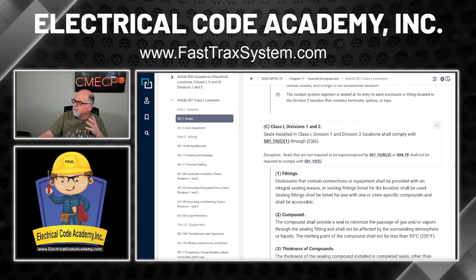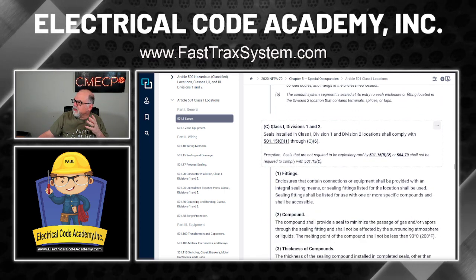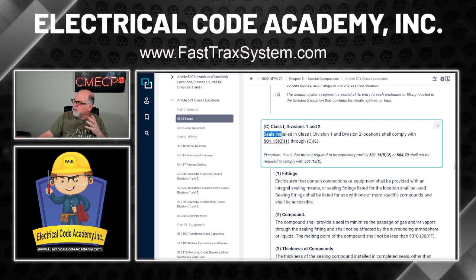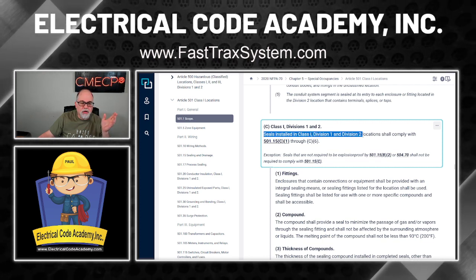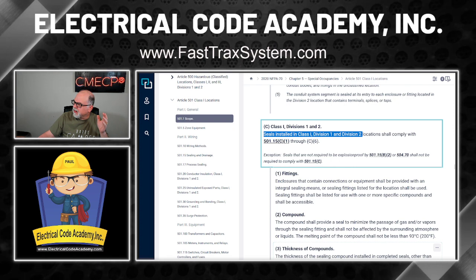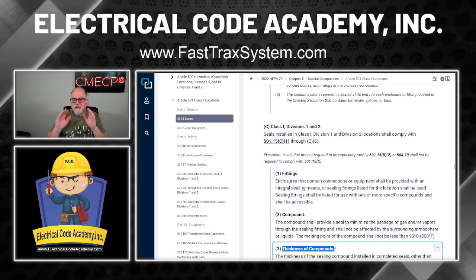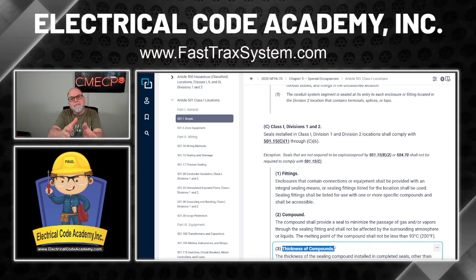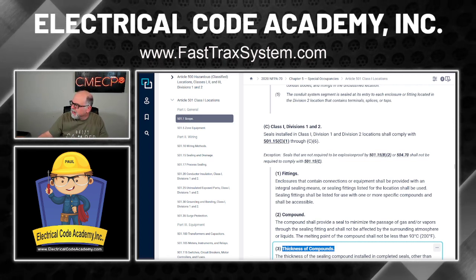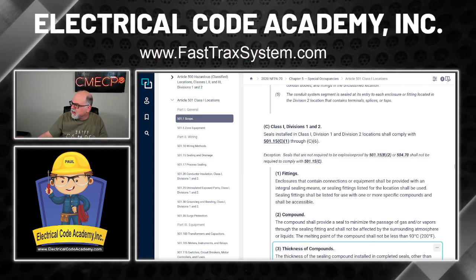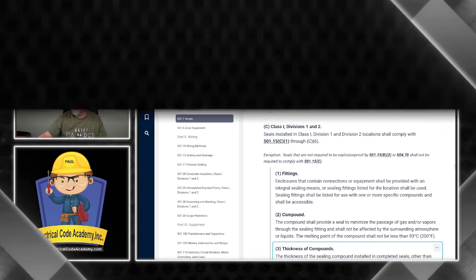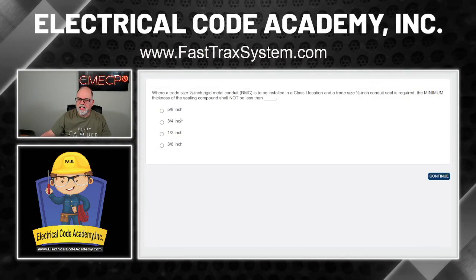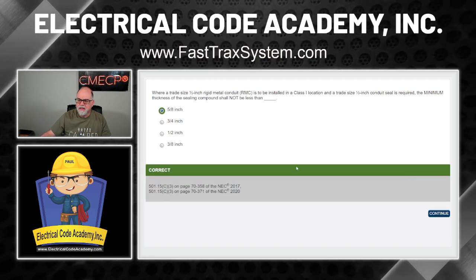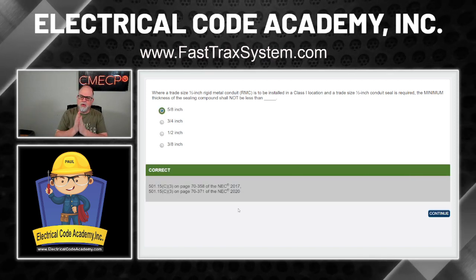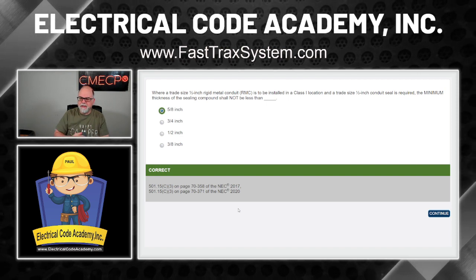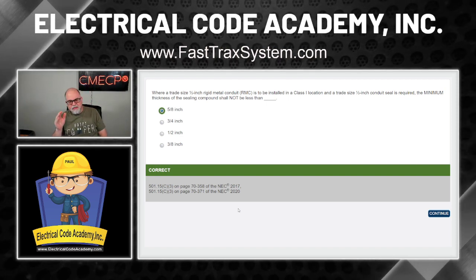We're doing this quickly. And then we come down here and we see Class 1. This is seals installed in Class 1. It doesn't matter, Division 1 or Division 2. And then notice we see something down here that says thickness of compounds. Does that not basically match what we saw in the question? All right. And the first thing your eyes need to go to is you'll see 5/8 of an inch, right? So you go back over to the question and you go, boom, 5/8 of an inch. And there it is. 501.15 C3.